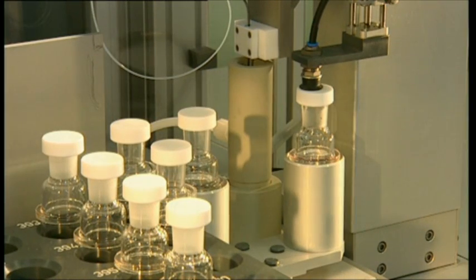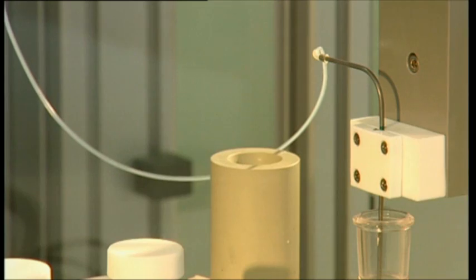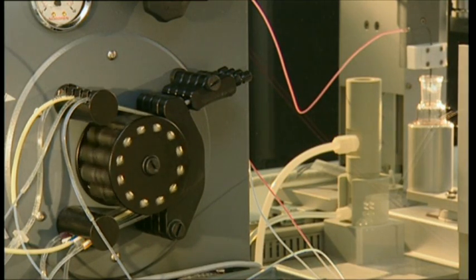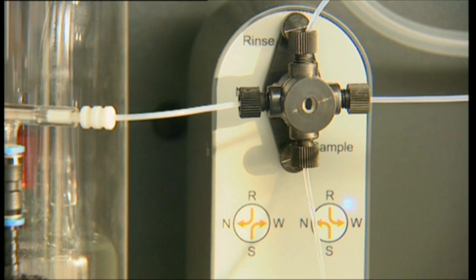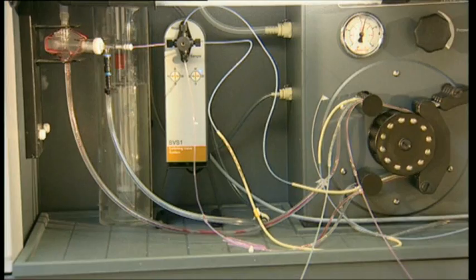The bottle is placed on a turret device and sampling takes place. A small portion of the liquid is transferred to the spectrometer through a peristaltic pump, visible on the lower right-hand side of the system. A valve allows the user to switch rapidly between the digestion solution and cleaning solution. This shortens the measuring times considerably and, just as importantly, minimizes sample consumption.